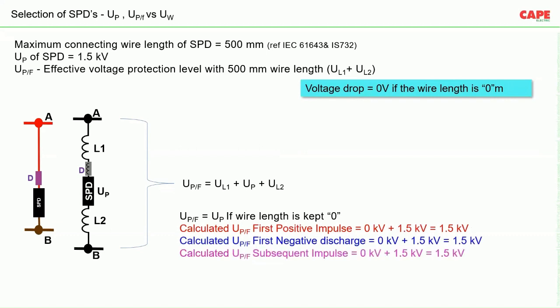The best-case scenario is a wire length of zero meters. With zero wire length, the calculated UPF for the first positive, first negative, and first subsequent impulses are all equal to just 1.5 kV — only the SPD's own protection level. Since there is no wire, there is no voltage drop, and di/dt becomes irrelevant, irrespective of the lightning protection level.